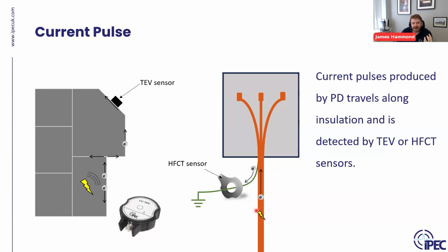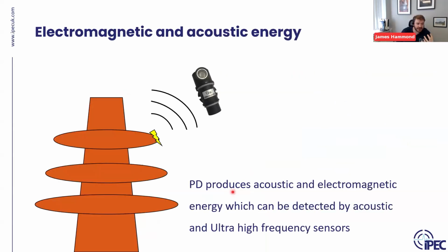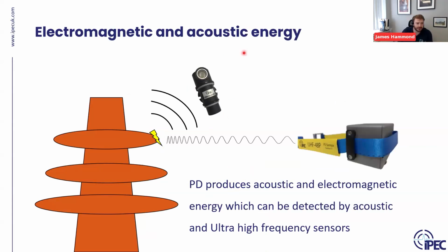And same method in cables as well. You get that movement of electrons, which then travels down the earth, in this case, where we put our sensors, and again, induces that voltage. So then we can detect this partial discharge. For acoustic, what we do is simply put a microphone. If you have your bushing, in this case, PD on the surface emits the energy acoustically and can be detected by the microphone.